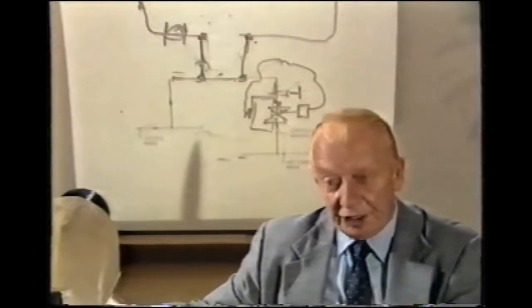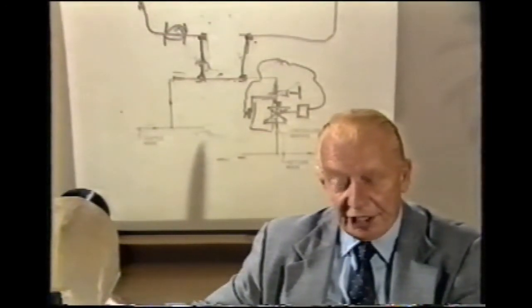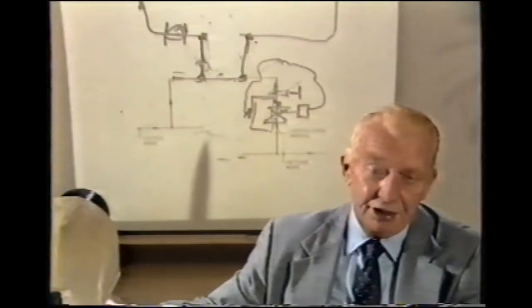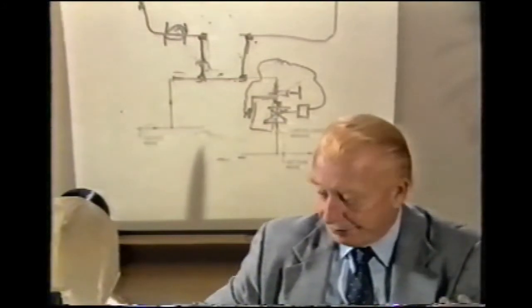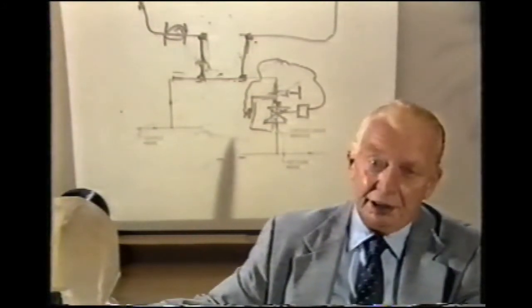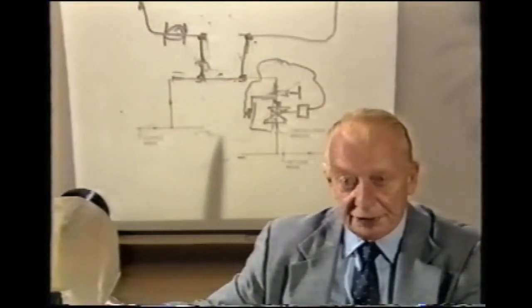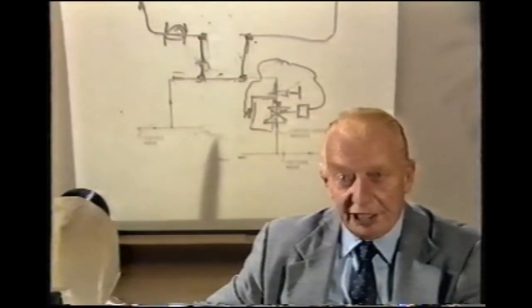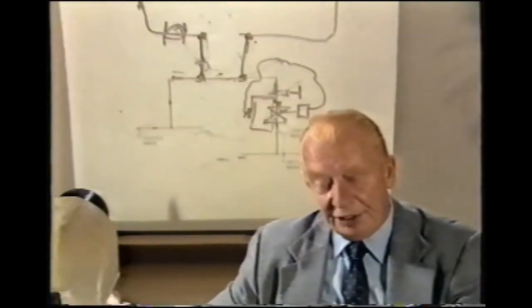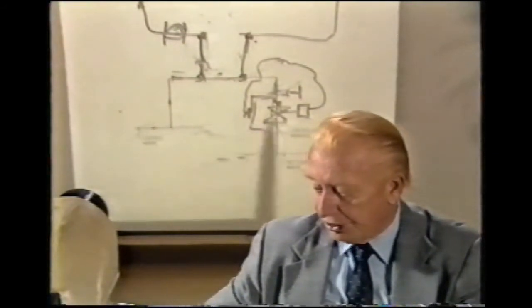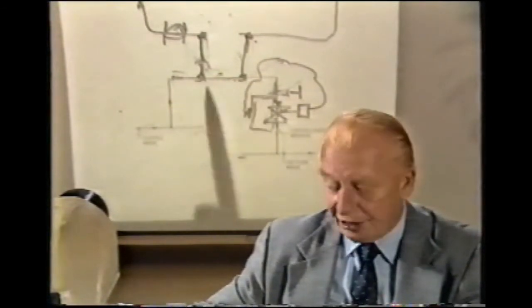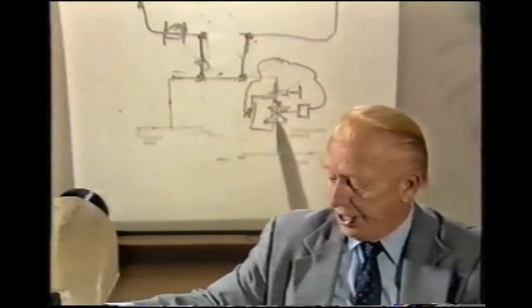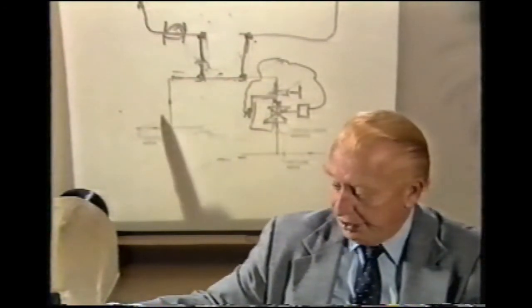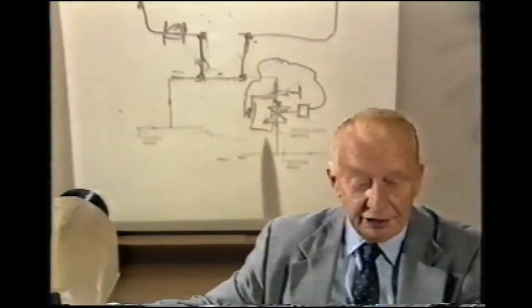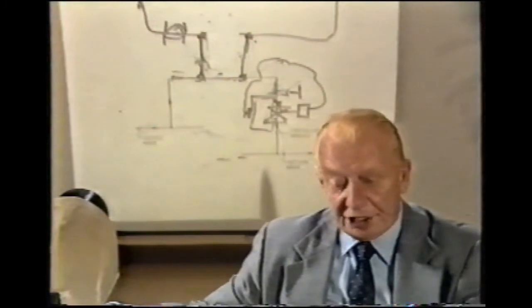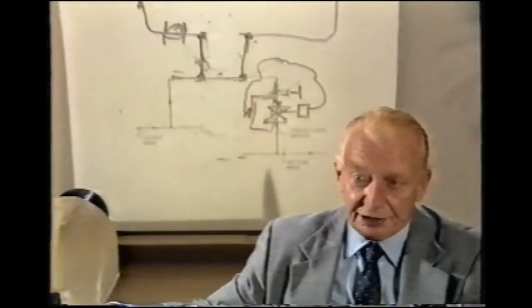So we have established then that we can control primary, secondary circuits, whether these be storage tanks, vats, heating, cooling secondary circuits, by means of single pump, by means of injection pumping from the primary circuit and into the secondary, by means of three-way control valves, with the three-way control valves, if you will remember, being installed in the crossover bridge as a mixing valve, and/or by use of a two-way control valve installed in either the supply or return leg of the secondary circuit. And this provides us then with a great variety of potential control methods.